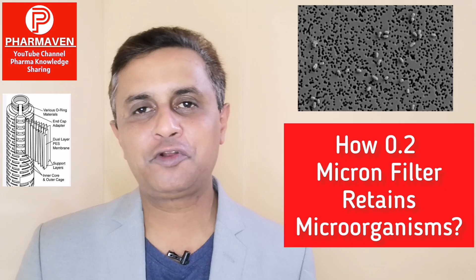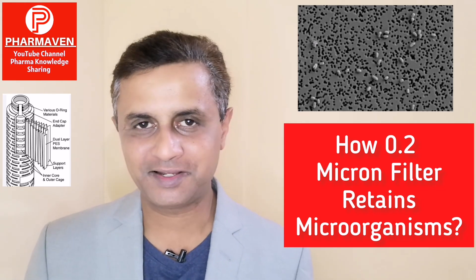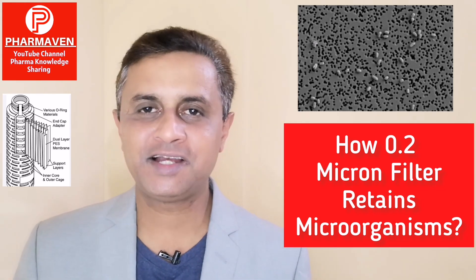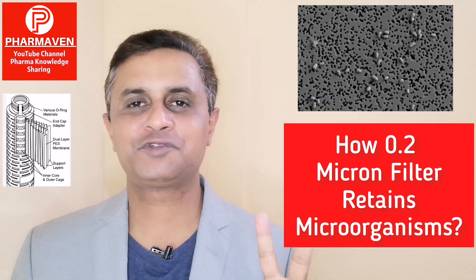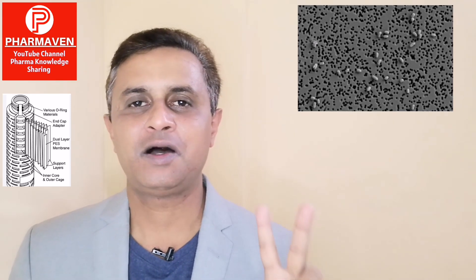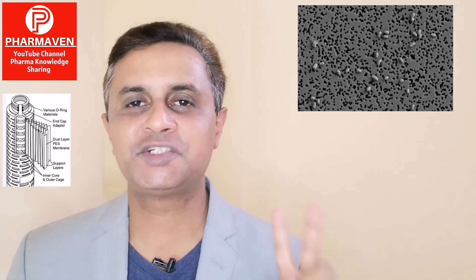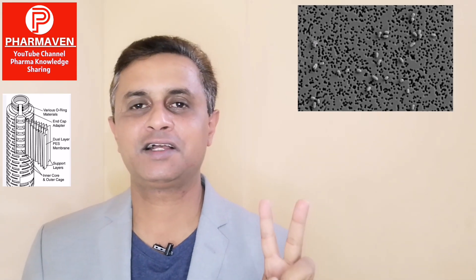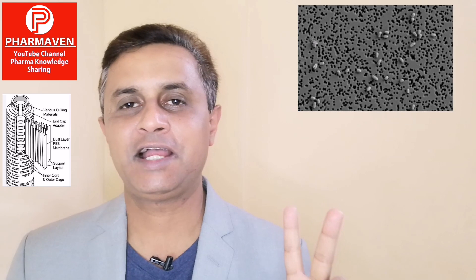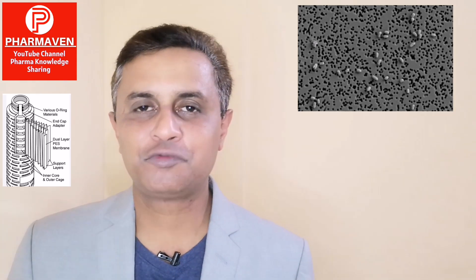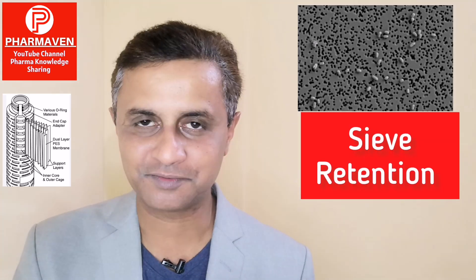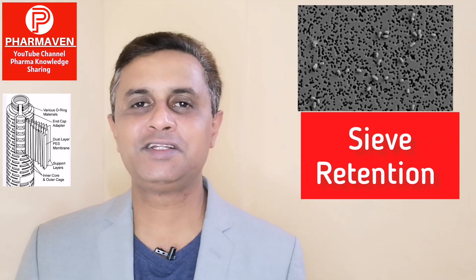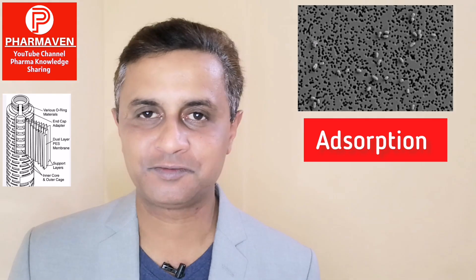In today's video, we will understand how a 0.2 micron filter retains bacteria — what is the science behind it. There are two mechanisms by which a 0.2 micron pore size filter retains bacteria of 0.2 micron size and above. One is retention by sieving — physical retention — and the second is retention by adsorption, which is a charge-related mechanism.